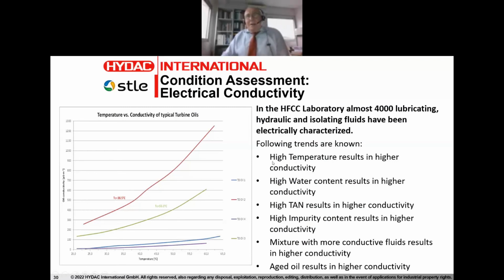Now let's switch topic for yet another side. We are always searching for new and improved condition monitoring parameters that would tell us something about the fluids. And one of them that we have stumbled upon is conductivity. Conductivity is very varied amongst different oil types. It depends on, again, the oil base stock type, the additive content, and so on. But it can tell us a lot about the oil type and about the changes occurring within the fluid. This is not an online sensor, I want to emphasize. This is an offline sensor. But we're working on developing an online one.